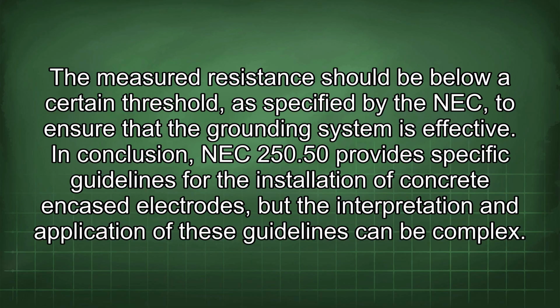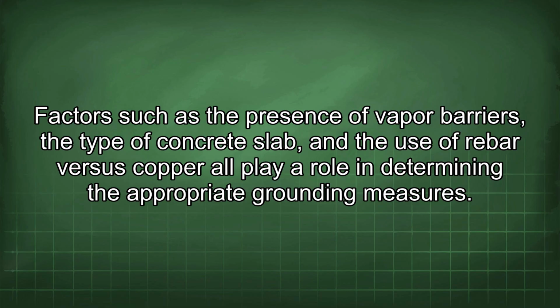The measured resistance should be below a certain threshold, as specified by the NEC, to ensure that the grounding system is effective. In conclusion, NEC 250.50 provides specific guidelines for the installation of concrete encased electrodes, but the interpretation and application of these guidelines can be complex. Factors such as the presence of vapor barriers, the type of concrete slab, and the use of rebar versus copper all play a role in determining the appropriate grounding measures.